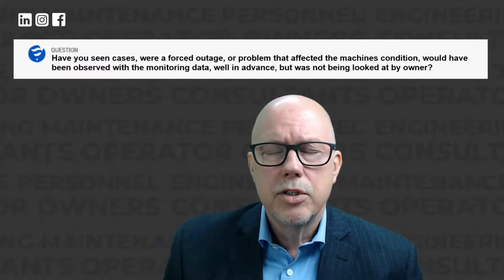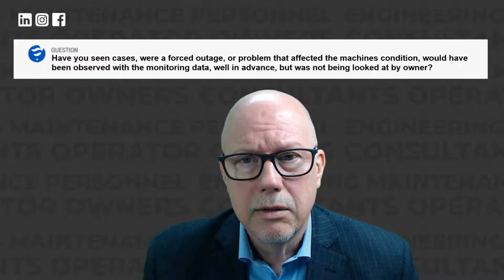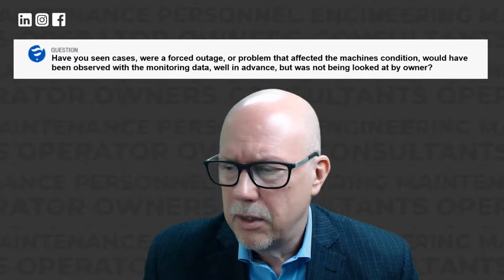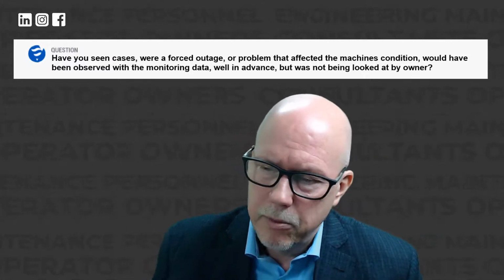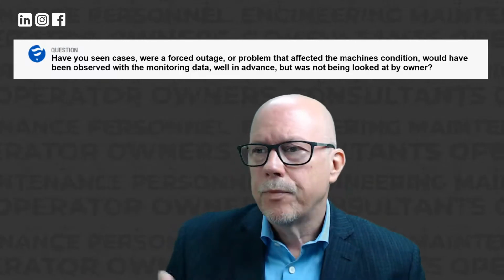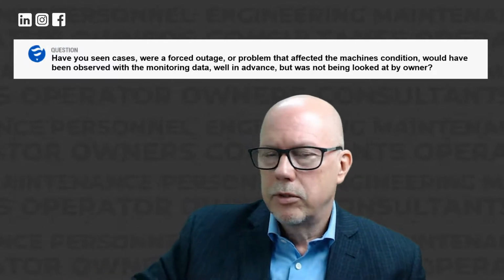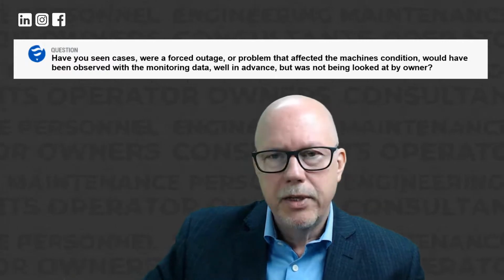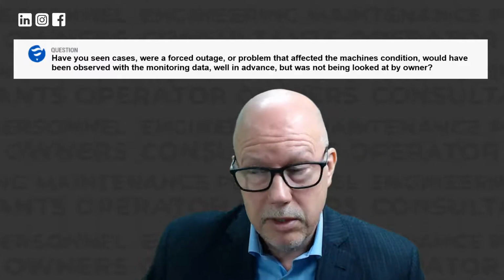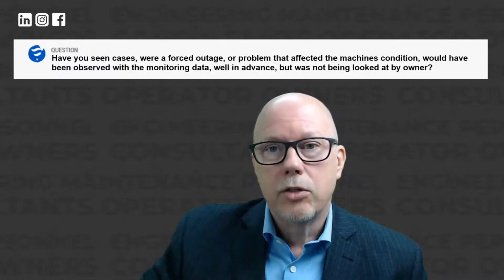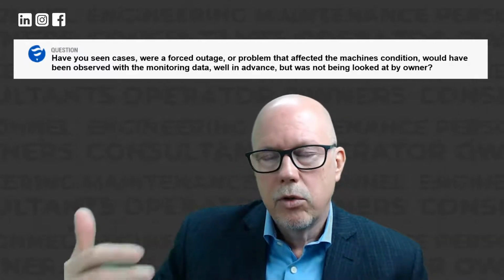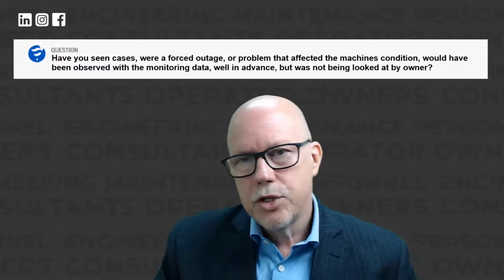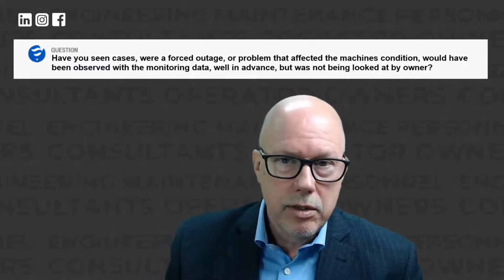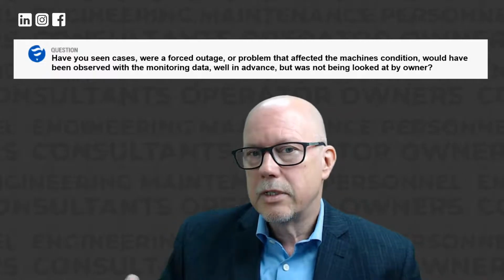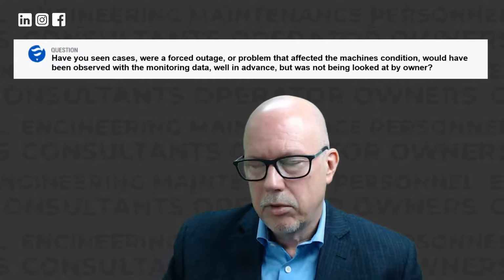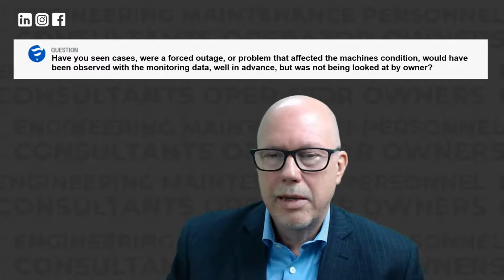And in most cases, those issues are not only left unchecked, but nobody's even aware that the problem exists, because most people look at the vibration results that go into their SCADA system or their PLCs from the perspective of peak displacement. That is important, of course, because it's how severely the shaft is moving, and there are tolerances for that. But if you have a rotor that's not centered, when you apply the field, that rotor will shift to where the magnetic field is strongest, where the air gap is smallest, and it will stay there. So it's magnetically coupled. The unit is almost unable to move.